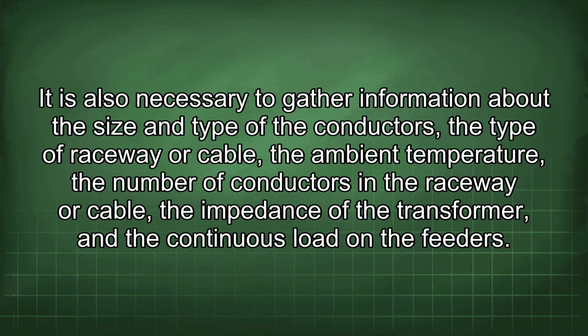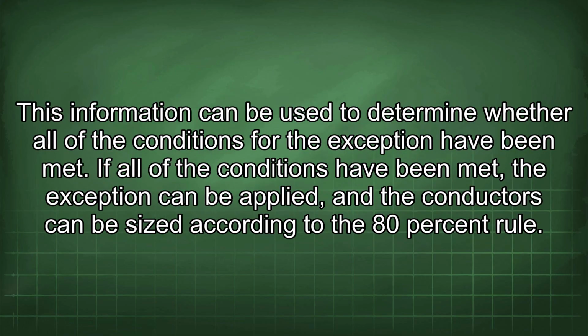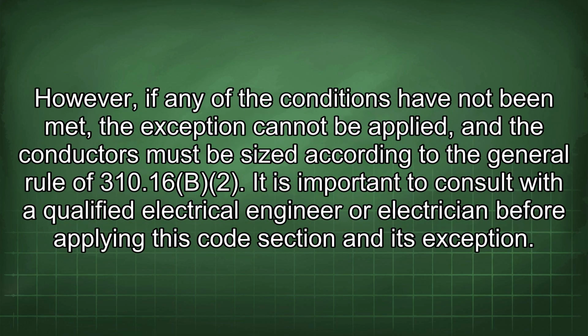It is also necessary to gather information about the size and type of the conductors, the type of raceway or cable, the ambient temperature, the number of conductors in the raceway or cable, the impedance of the transformer, and the continuous load on the feeders. This information can be used to determine whether all of the conditions for the exception have been met. If all of the conditions have been met, the exception can be applied and the conductors can be sized according to the 80% rule. However, if any of the conditions have not been met, the exception cannot be applied and the conductors must be sized according to the general rule of 310.16(b)(2).